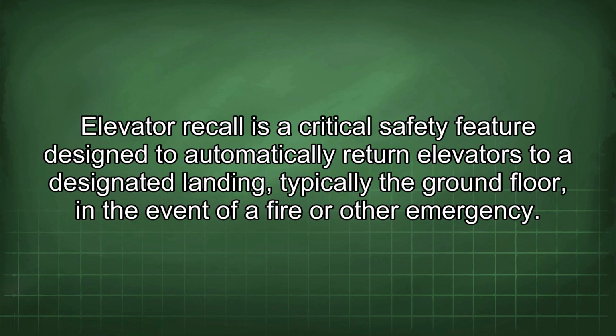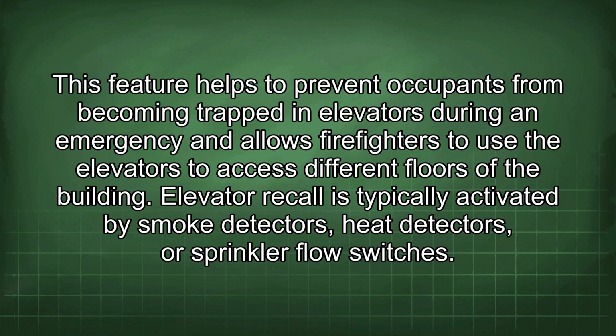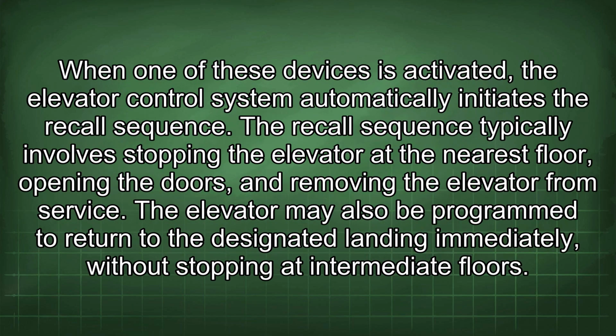Elevator recall is a critical safety feature designed to automatically return elevators to a designated landing, typically the ground floor, in the event of a fire or other emergency. This feature helps to prevent occupants from becoming trapped in elevators during an emergency and allows firefighters to use the elevators to access different floors of the building. Elevator recall is typically activated by smoke detectors, heat detectors, or sprinkler flow switches.